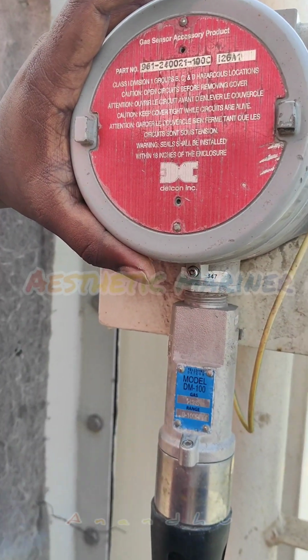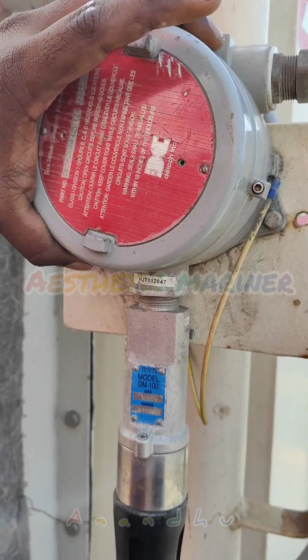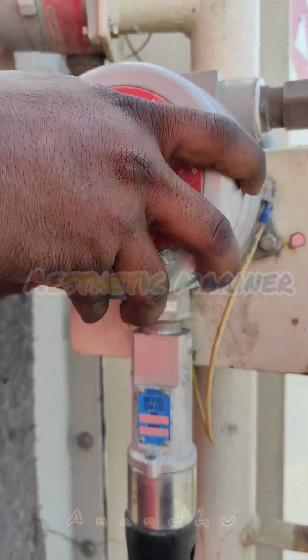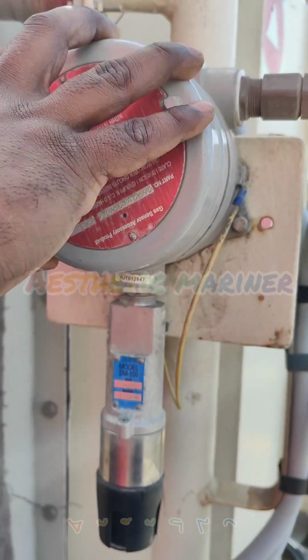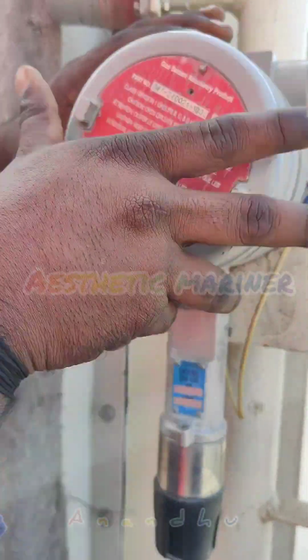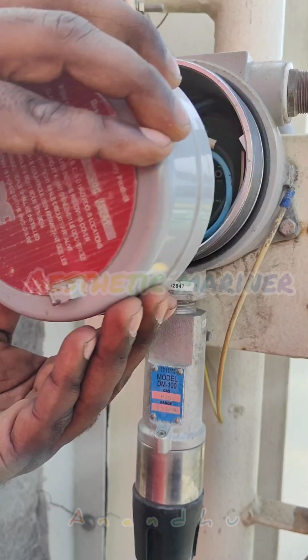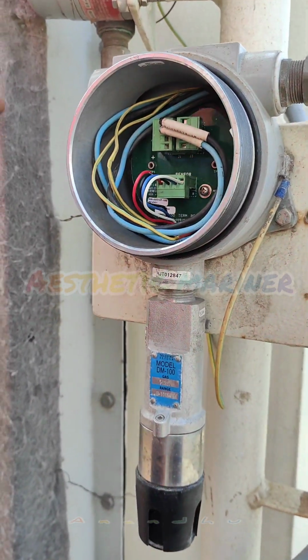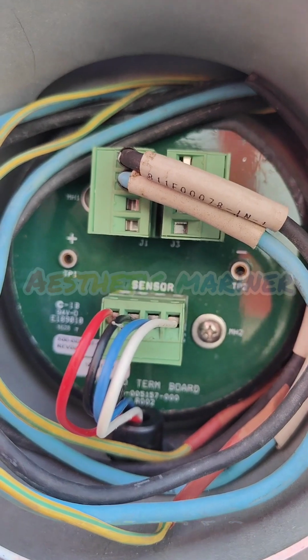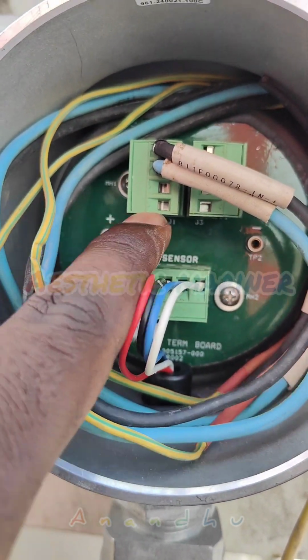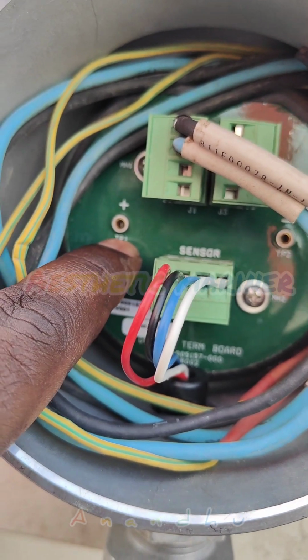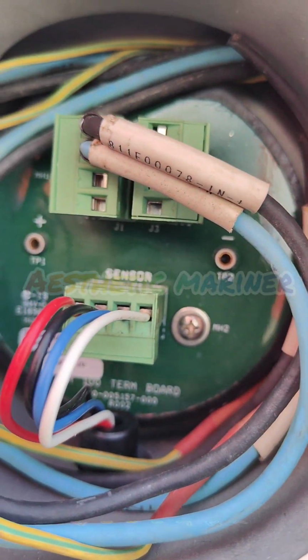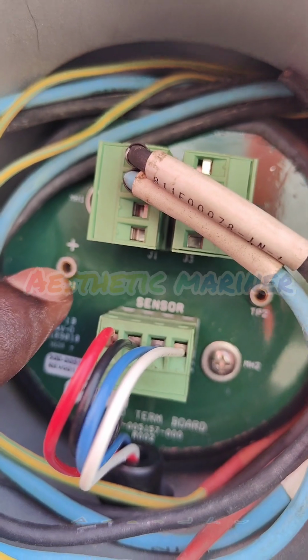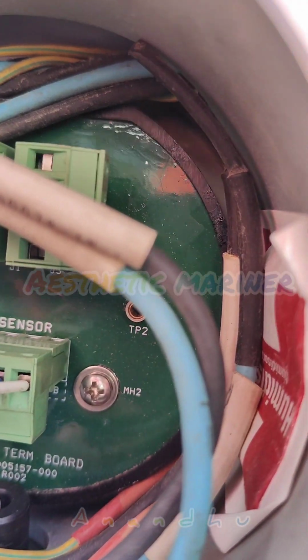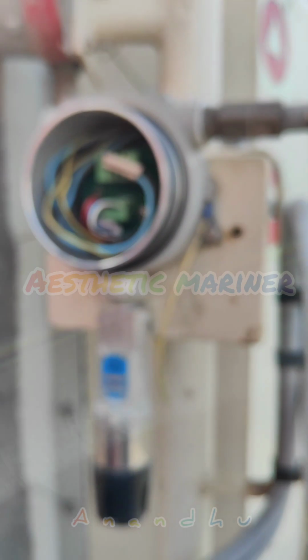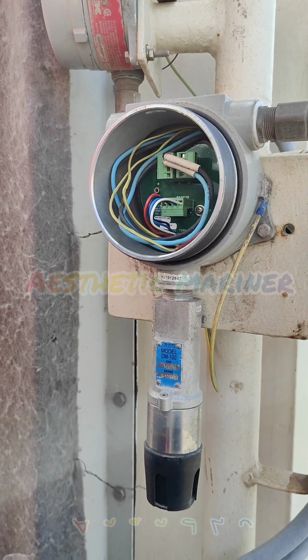Before the calibration, we just remove this cover. Now we have opened the cover, and we can see the inside connections. This is the sensor connection and this is the signal connection. This is a two-wire method. Here we can see the two ports, TP1 plus and TP2 minus. These are the ports where we are going to keep our multimeter, TP1 and TP2. For the calibration method, we use the multimeter to check the reading.